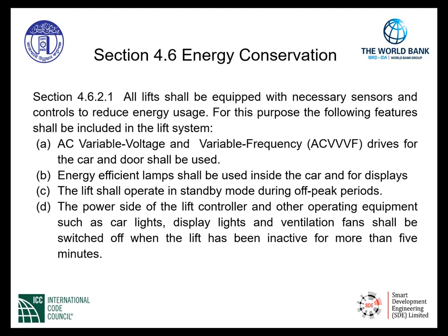Item A indicates that AC variable voltage and variable frequency drives for the car and door shall be used. B, energy efficient lamps shall be used inside the car and for displays. This would produce lower power consumption, of course, when we use energy efficient lamps. Some of the lamps that we utilize in modern technology are the LED type of lamps.